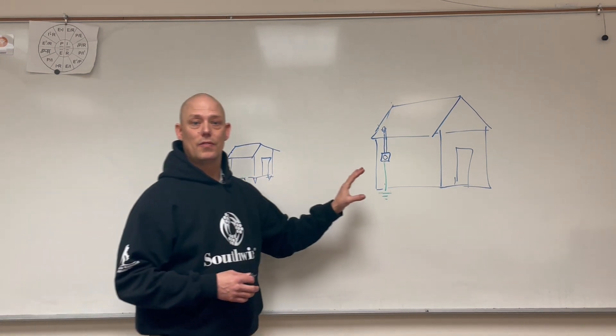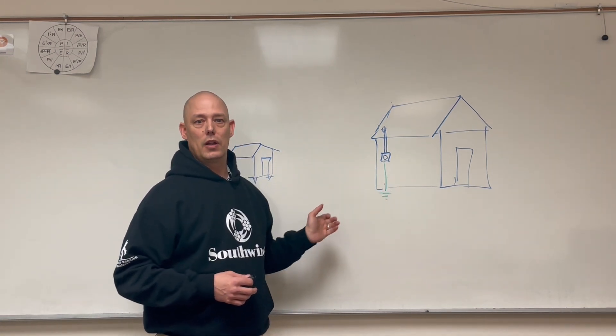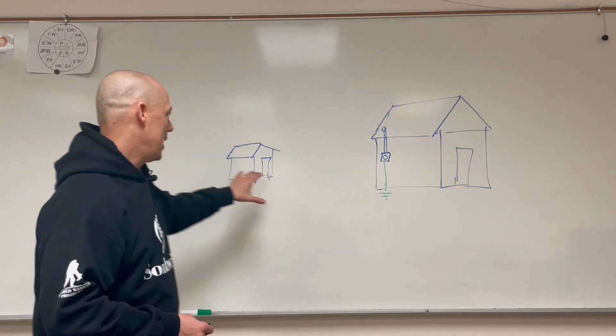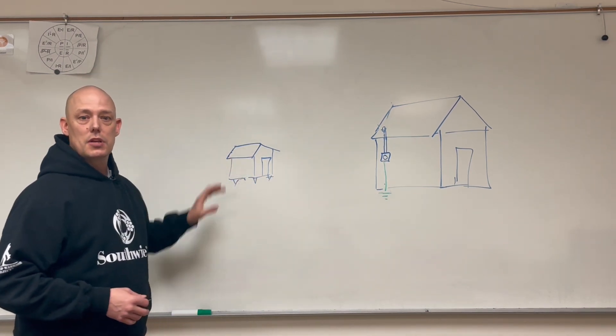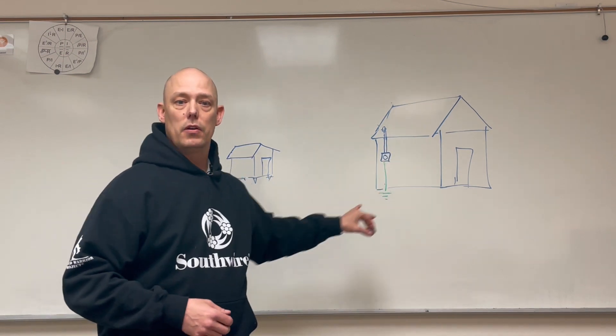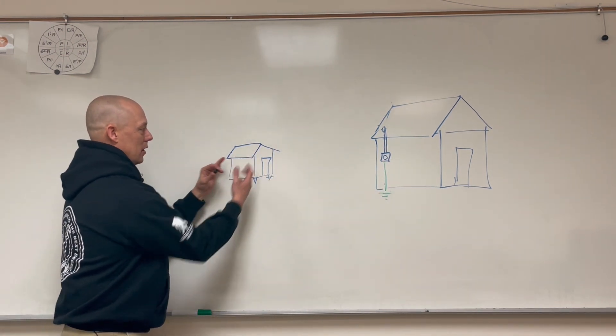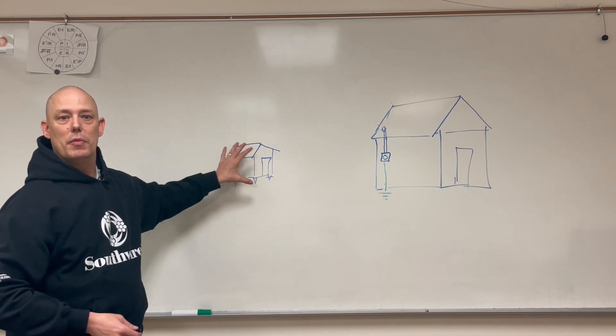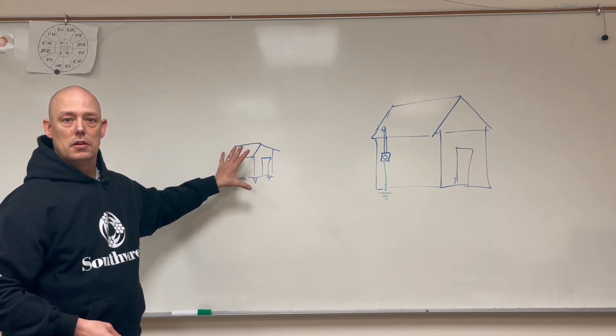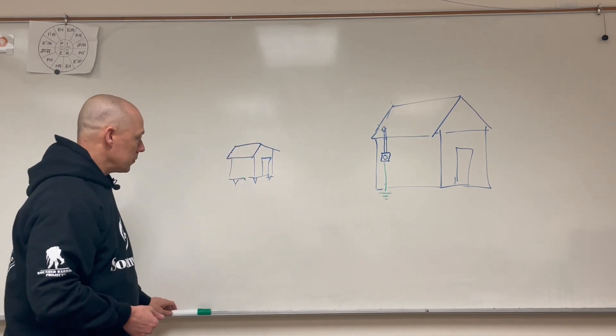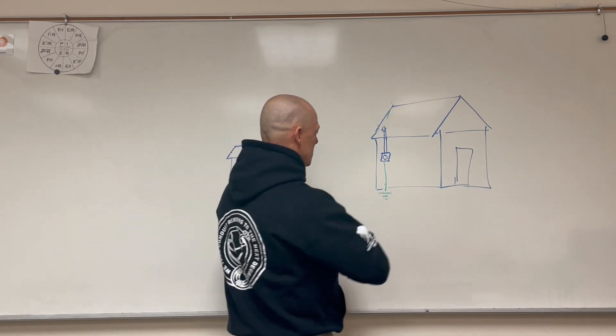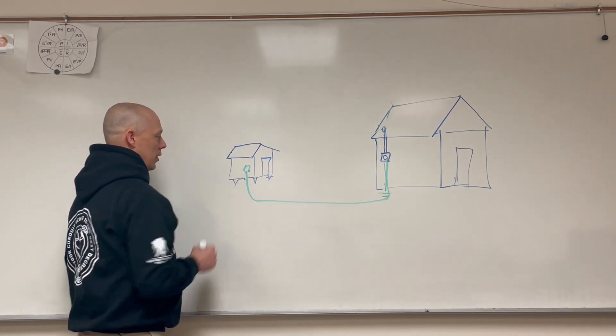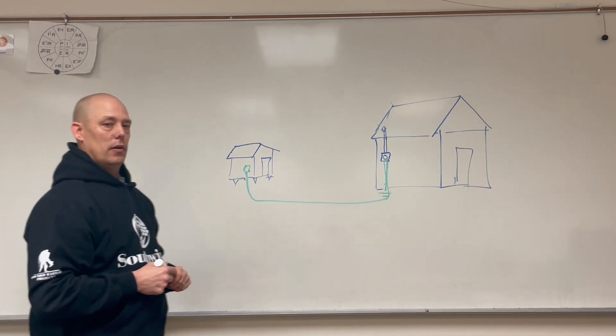That would violate 225.30, which tells me I can only have one. So then we know we would have to put a subpanel out here. If we put a subpanel out here, that's one feeder, and from that subpanel I could put multiple branch circuits or pieces of equipment in this building. I'm going to take a feeder underground and put a panel out there.